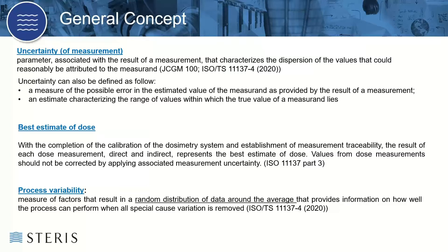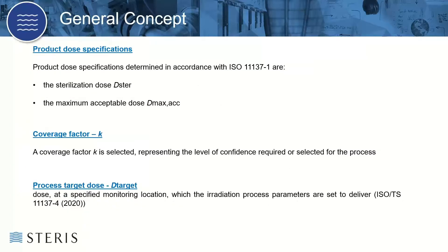Process variability is a measure of the factors that result in random distribution of data around the average, providing information on how well the process can perform when all special cause variation is removed. Special cause variation is variation that is unpredictable or outside our historical experience base. We'll look at product dose specifications: the product dose specification is the range of acceptable dose that can be delivered to a product, which is established during dose setting validation.